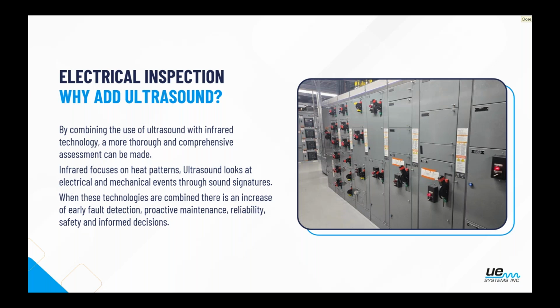So what infrared is looking for is your resistance issues. So events that are going to create heat, whereas ultrasound is actually looking for the friction caused by these electrical anomalies. So an example of what infrared might miss, but ultrasound would complement and pick up, would be something like a corona underneath 200,000 volts. That gives a very, very easy to detect and noticeable acoustic signal that we can pick up and then verify. So just using both of them together in that instance will help find all of the different forms of electrical anomalies that we're looking for, partial discharge.